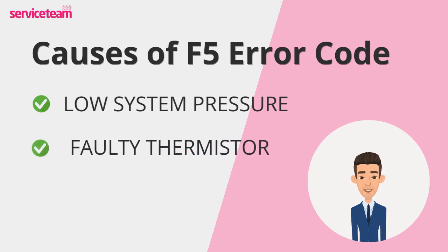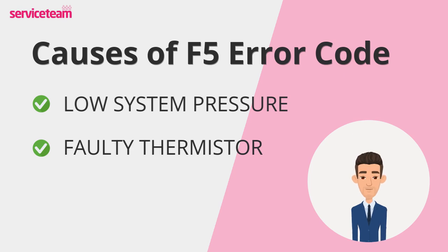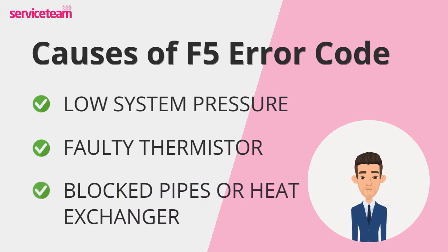Next, the cause is a faulty thermistor — it's like your boiler's temperature sensor. If it's not doing its job, the system can't measure the water temperature correctly, leading to errors. Over time, things like sludge, limescale, or debris can block your pipes or heat exchangers. This restricts water flow and causes the boiler to act up.